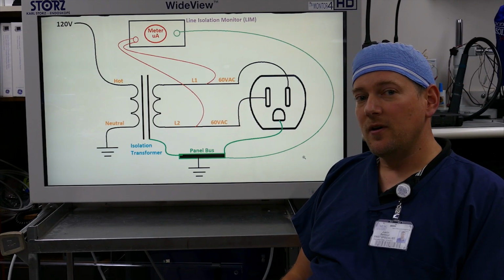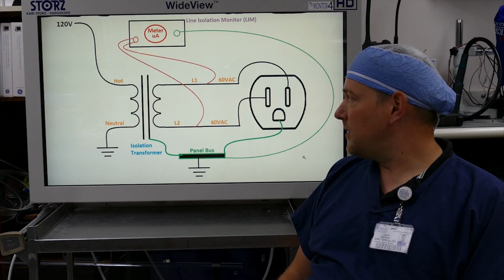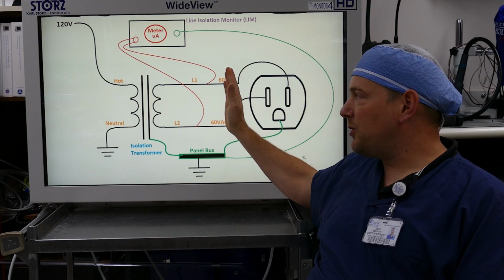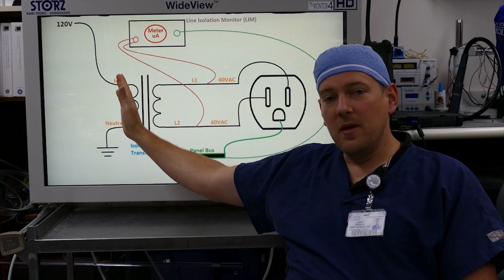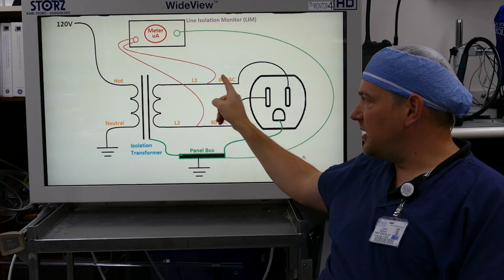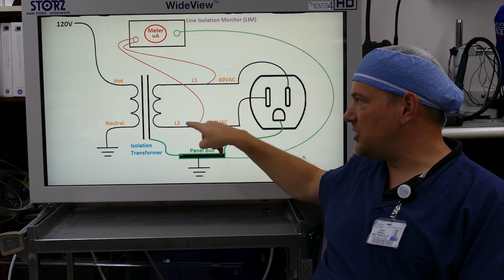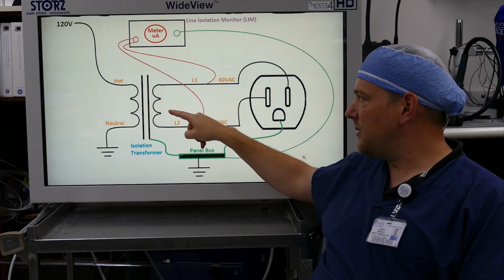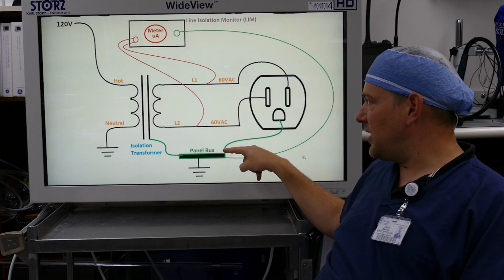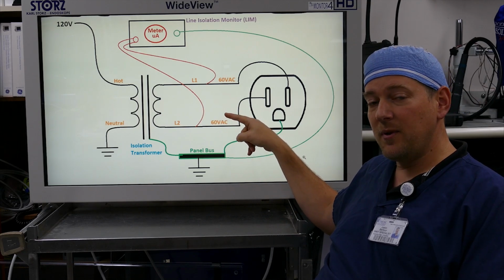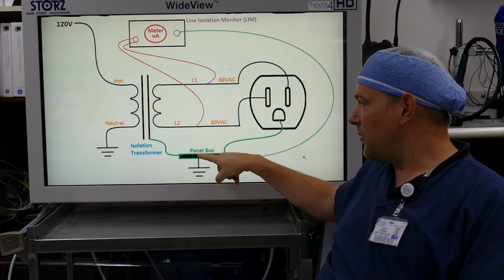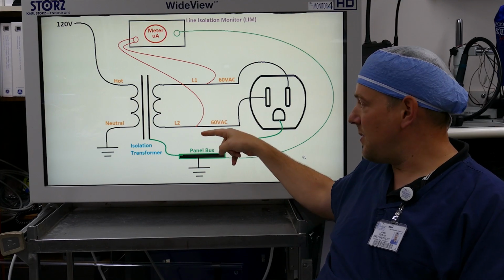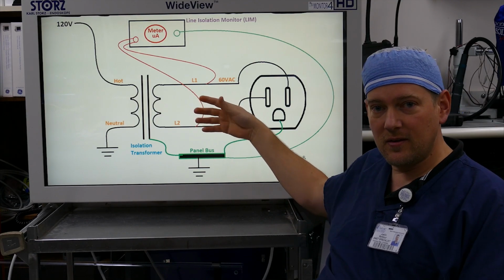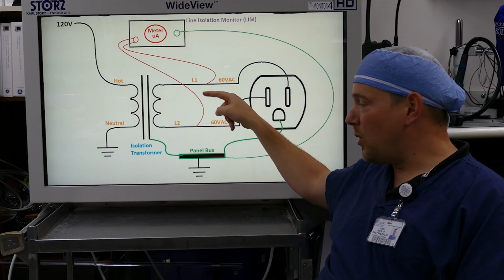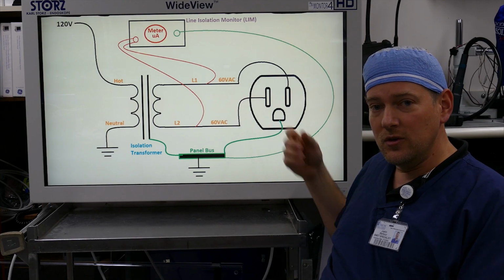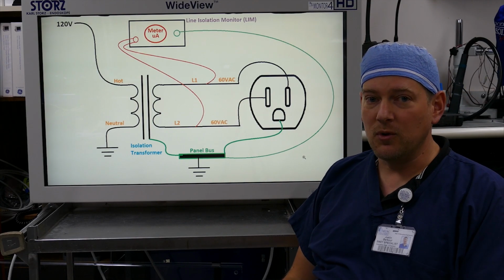So the concept of an isolated power system is to isolate the operating room from the mains. Electricity is looking to flow back to the point of origin, which is through the secondaries. You are at ground potential, and electricity generally will take the path of least resistance to its origin, which, as you can tell, ground is not part of the origin. The secondaries are. So unless you touch L1 and L2, you won't normally get shocked in an operating room environment.